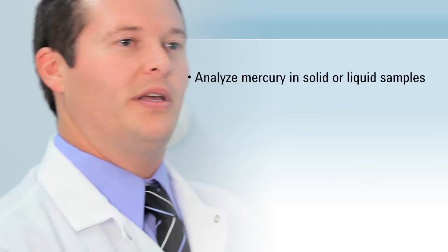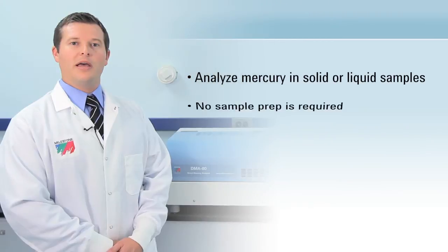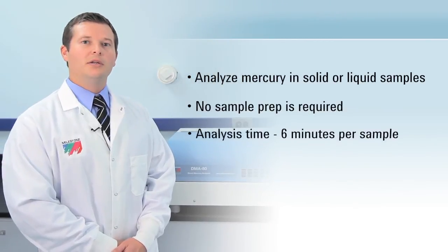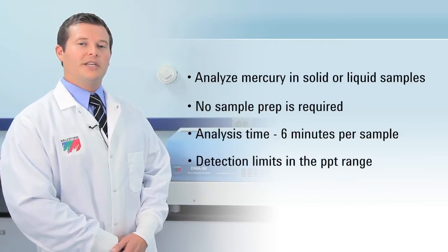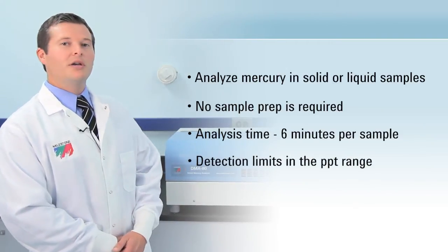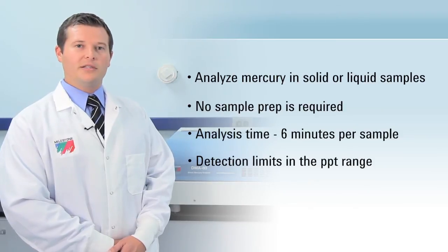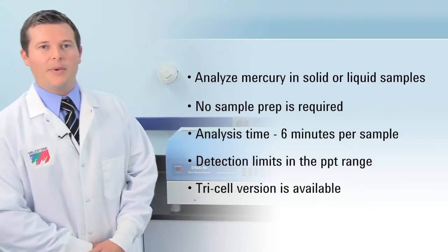The DMA80 can analyze mercury in solid or liquid samples, and no sample prep is required. Total analysis time is approximately six minutes per sample. Detection limits are in the PPT range, and for labs that require higher sensitivity, a tri-cell version of the DMA80 is available.